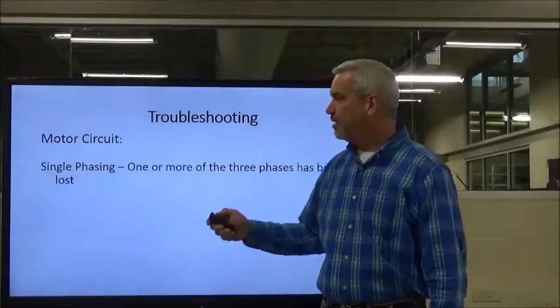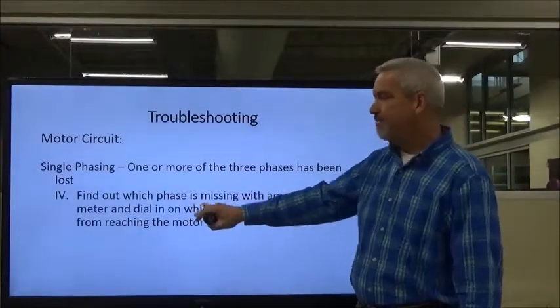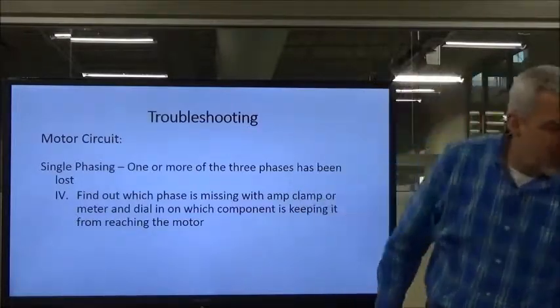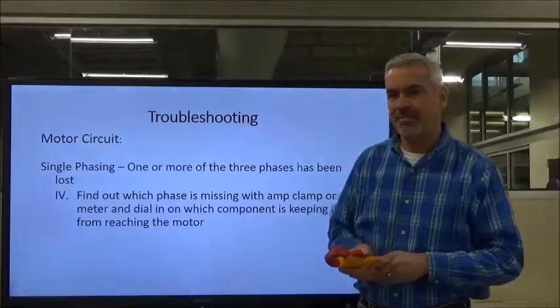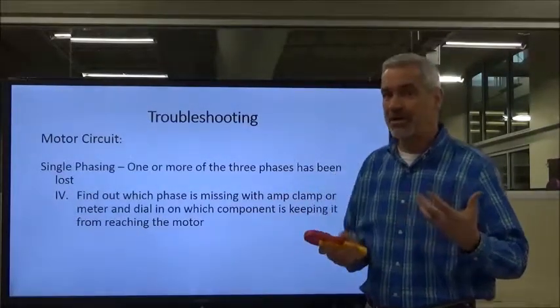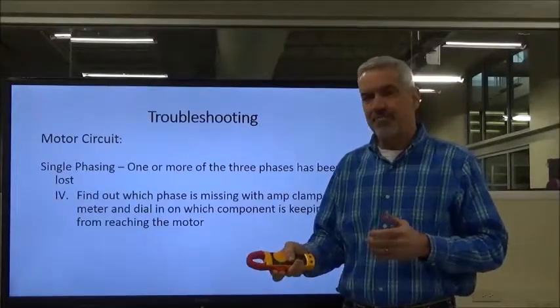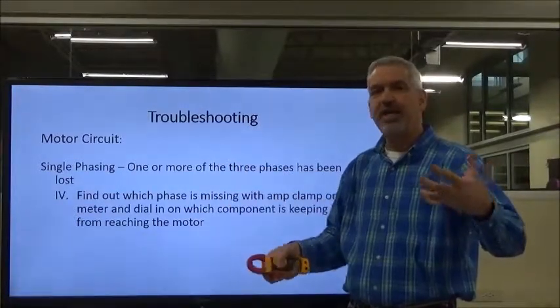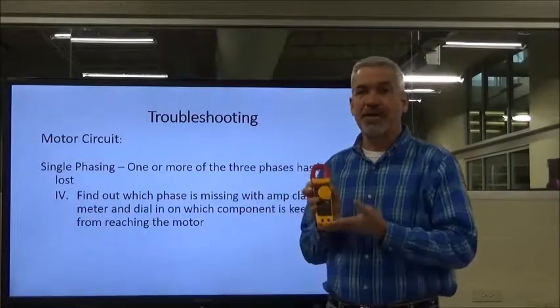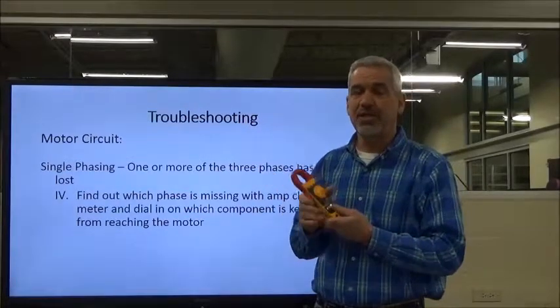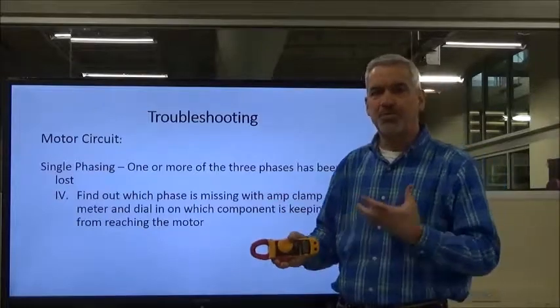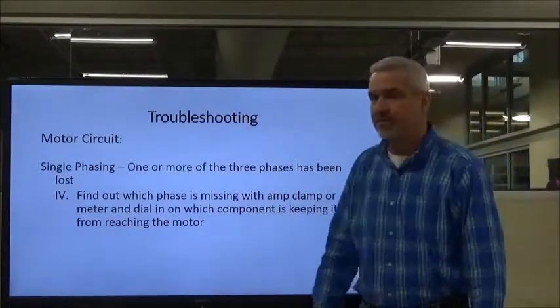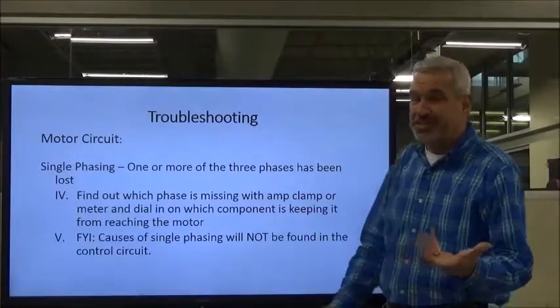Find out which phase is missing with an amp clamp — that's an easy way to do it. If you've got a single-phasing motor heating up quickly, be ready with your amp clamp. Have the operator start the motor and very quickly go between L1, L2, and L3 to find out which phase is missing — the missing phase won't pull any current, and the other two will actually pull more current than they should. You'll be able to very quickly clamp around and find the missing phase.